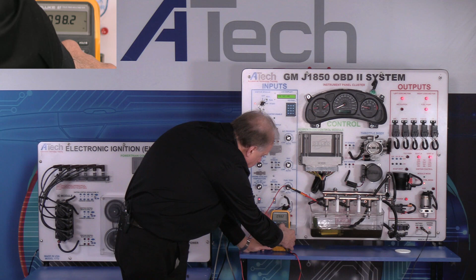Sometimes I can change, you have to change your trigger. We'll see if this one changes trigger right now. It didn't. So if you were looking at a meter, I would want to go over and figure out how to change my trigger. If not, I take what I've got right now, 98.2, and subtract that from 100%. What would that be? We're looking at about 1.8 percent on my duration. Other meters will allow you to change the trigger, and depending on what you've got, guys, it would make your diagnosis a little bit easier.